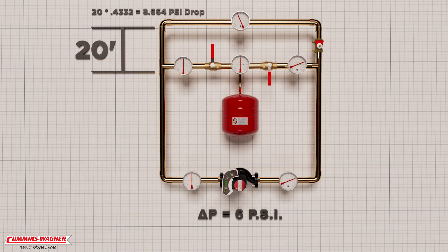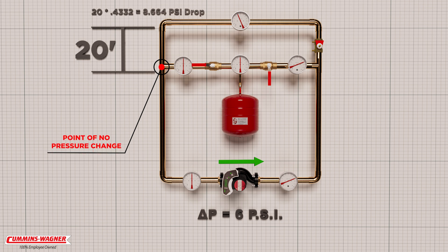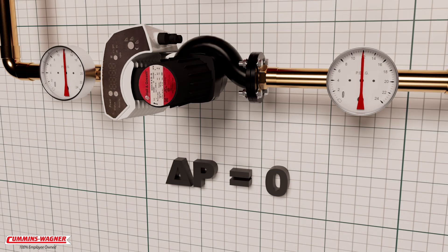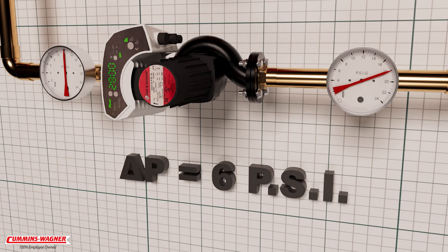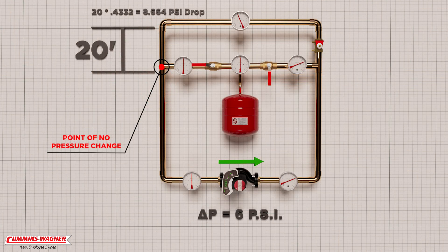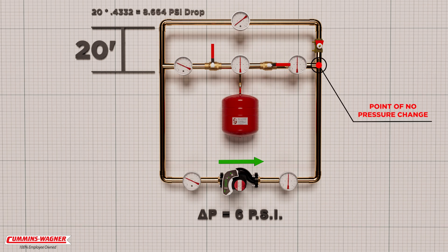Let's look at what happens when the expansion tank is open to the suction side of the circulator. In this correct scenario, we are pumping away from the expansion tank, or the point of no pressure change. As you can see, nothing really changes — the circulator is able to increase the discharge pressure and flow water to the top of the system. But if we open the other valve and move the point of no pressure change to the outlet of the circulator, we can see the immediate result.